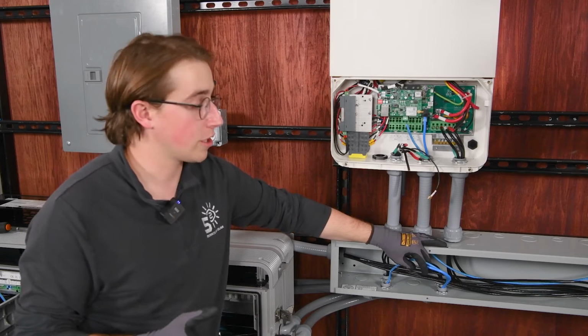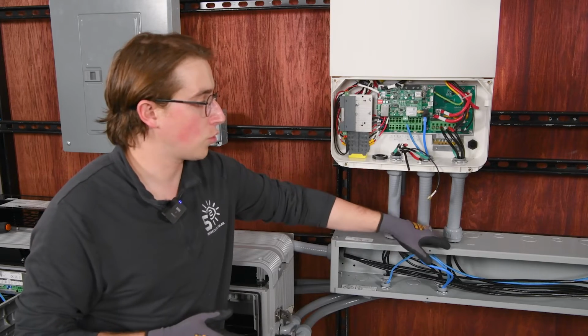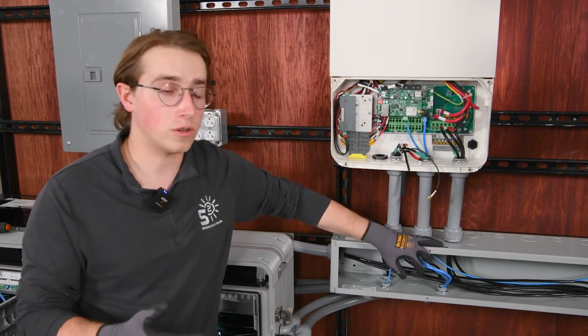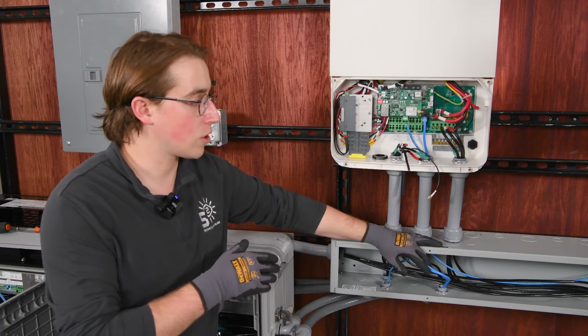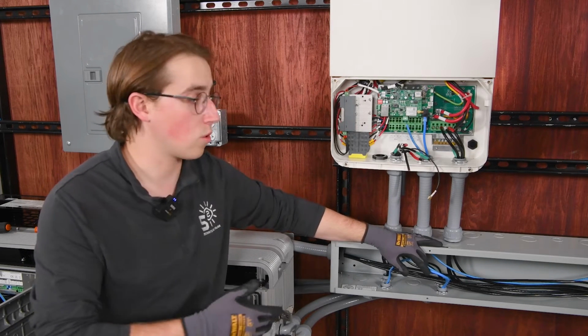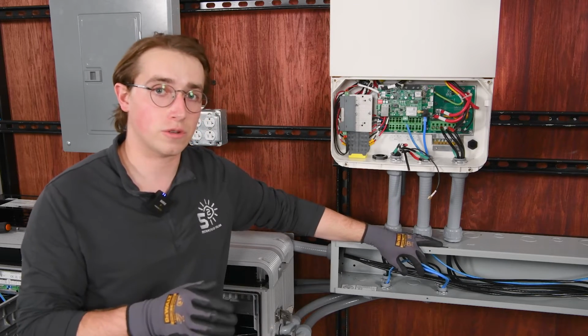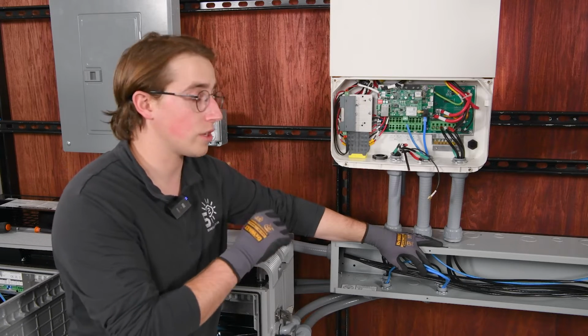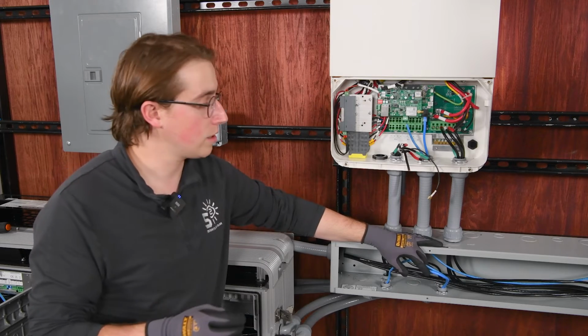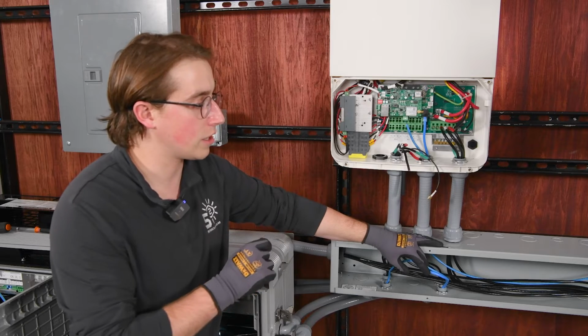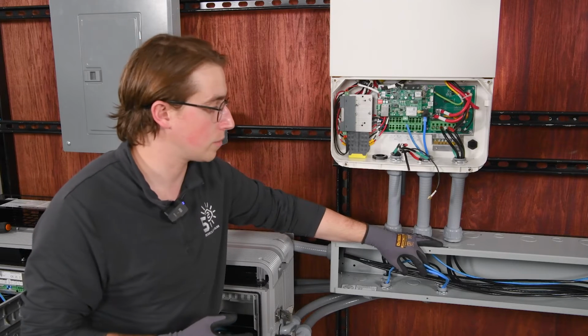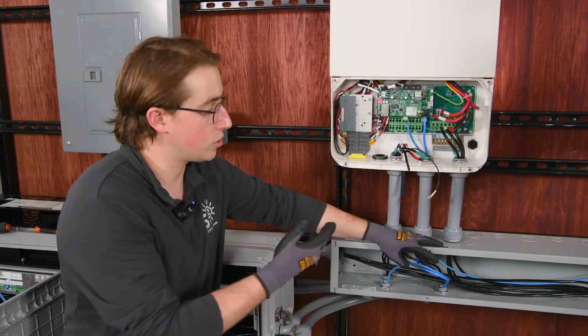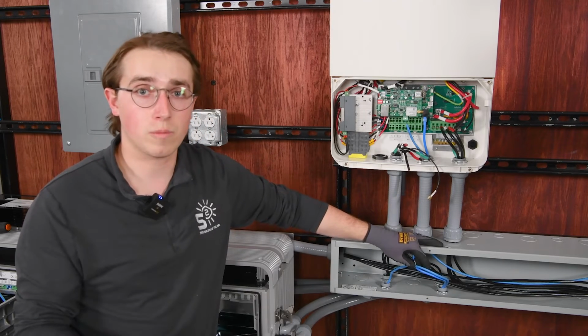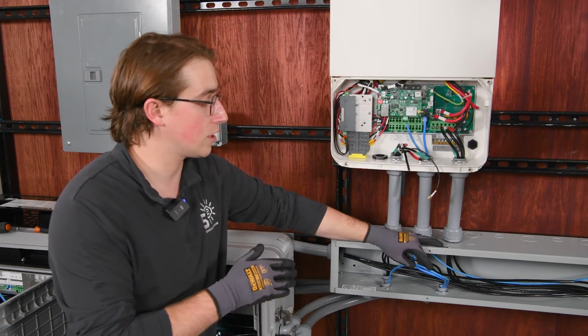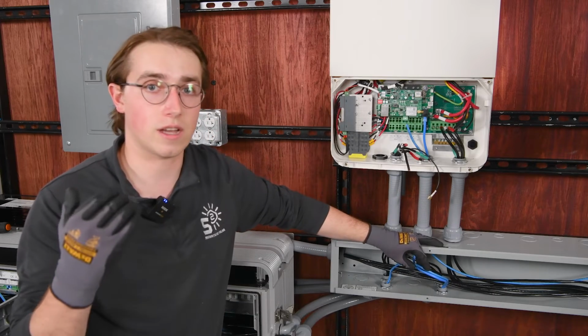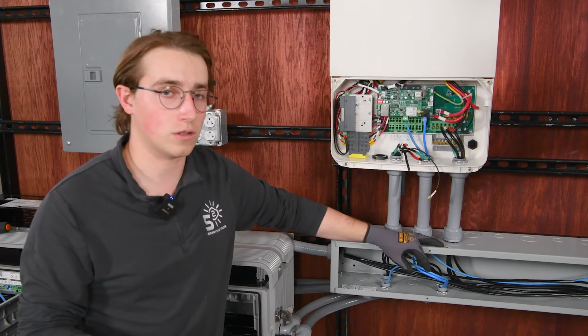When running communication cables through wire troughs, cable trays, or any conduit, if they're running in the same cable tray or conduit as hot conductors or high voltage cables, you'll need to make sure that the insulation of the communication cable is the same rating as the insulation of the hot conductors or the high voltage conductors that you're using. For this instance, we are just using standard Ethernet cable, but for code compliant installs, you'll need to make sure that that insulation rating is the same insulation rating as the hot conductors, which is typically around 600 volts.